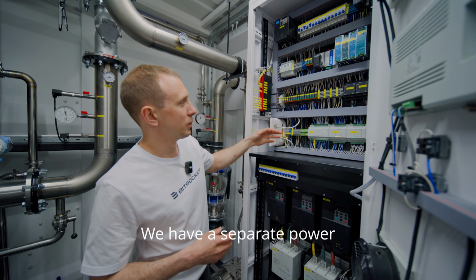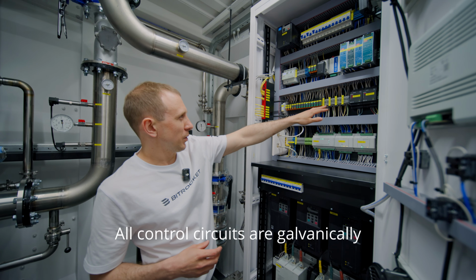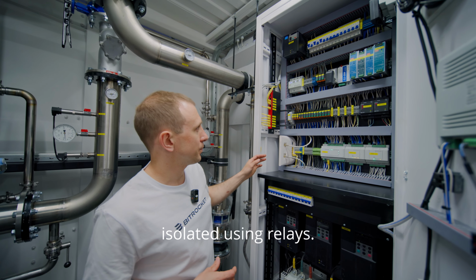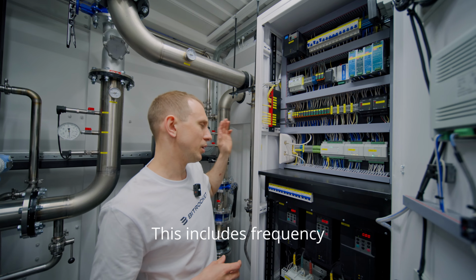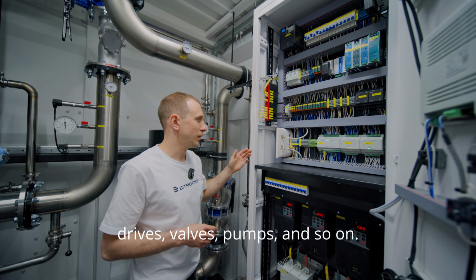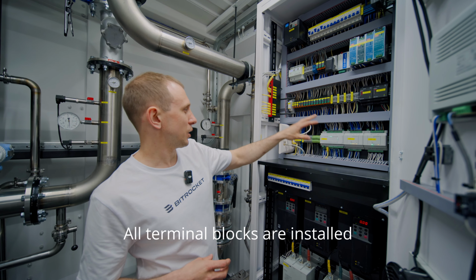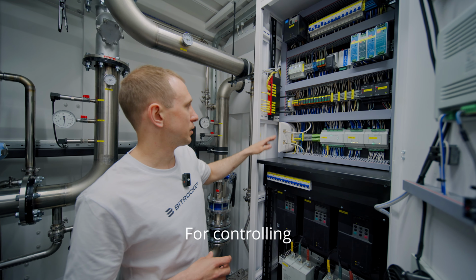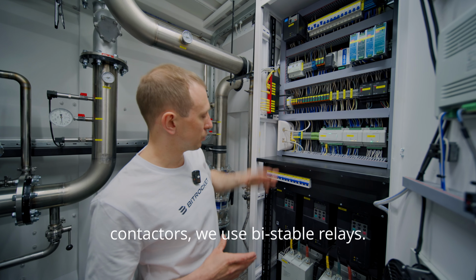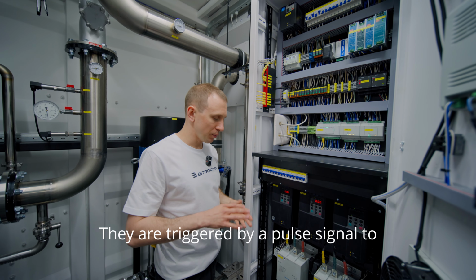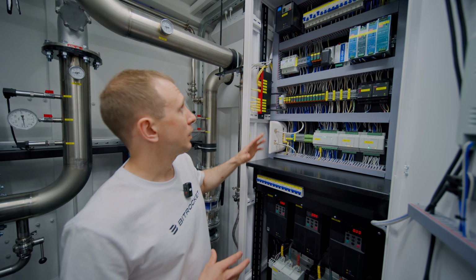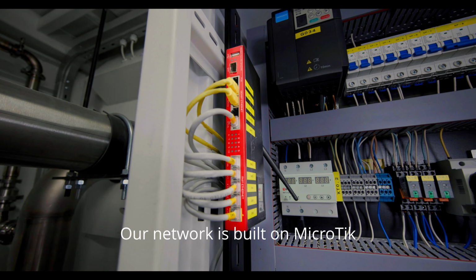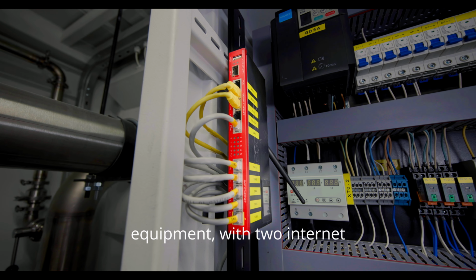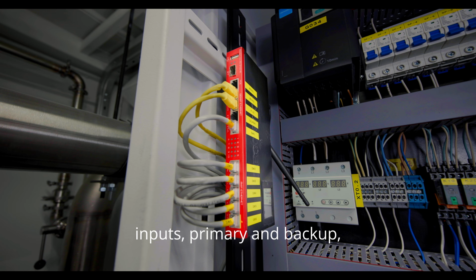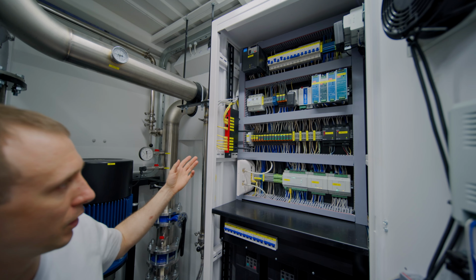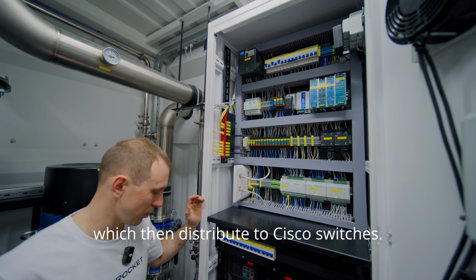We have a separate power supply unit for the valves. All control circuits are galvanically isolated using relays. This includes frequency drives, valves, pumps, and so on. All terminal blocks are installed according to the circuit diagram. For controlling contactors, we use bistable relays. They are triggered by a pulse signal to switch the contactor state. Our network is built on MikroTik equipment with 2 internet inputs, primary and backup, which then distribute to Cisco switches.